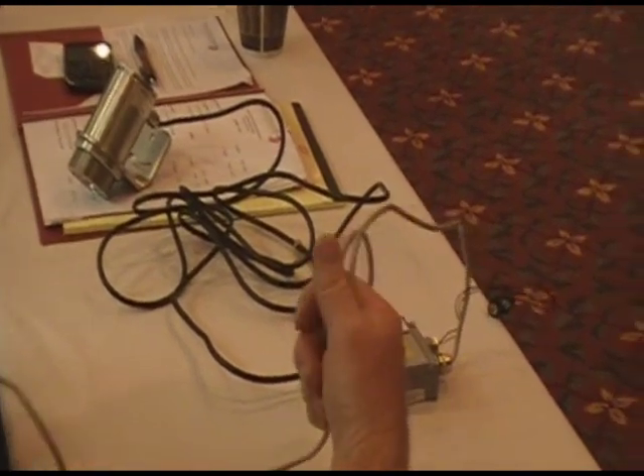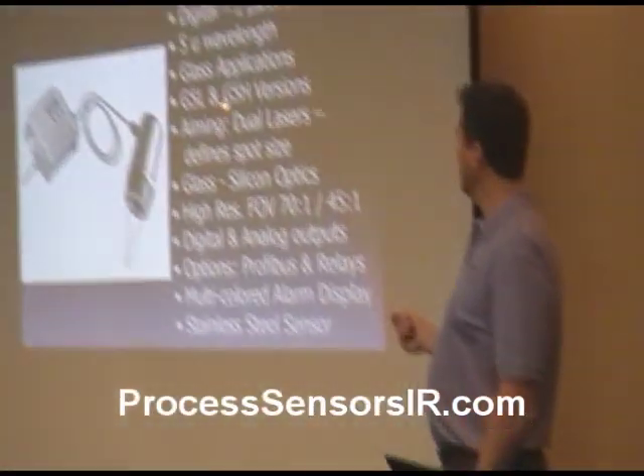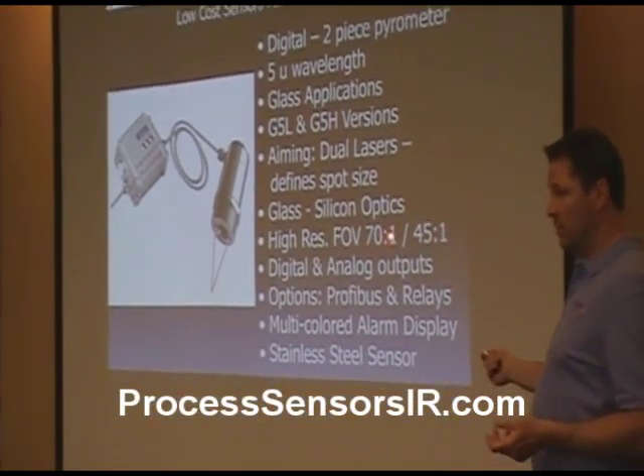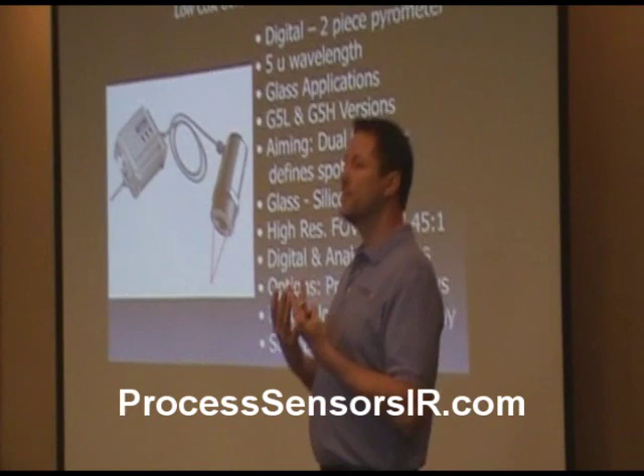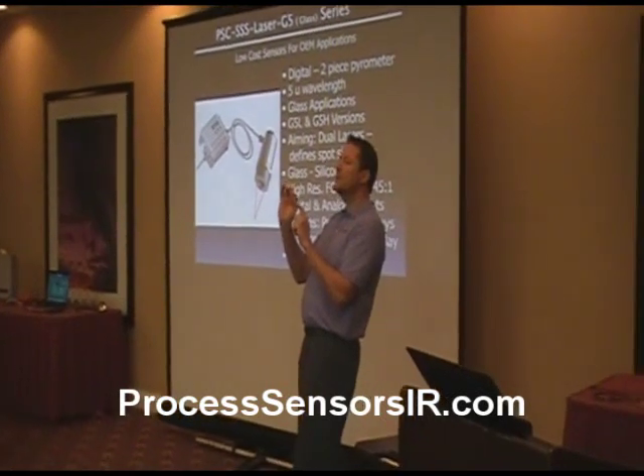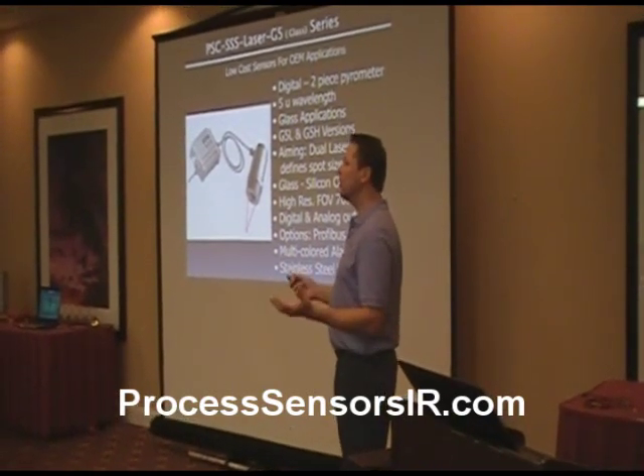This product also comes in a version with dual lasers and a few other wavelengths besides the short wavelength. It has a glass 5 micron wavelength, so it measures the surface of glass — you cannot see through the glass. There are two versions: G5 for glass 5 — L is the low temperature version, H is the higher temperature version. The L version is 45 to 1, the high temperature version is 70 to 1. Generally speaking, the higher the temperature, the smaller spot I can give you because you have more energy coming in, so you can reduce the aperture and get a smaller spot size. If you have less energy, you have to have a larger aperture and you get a larger spot size.